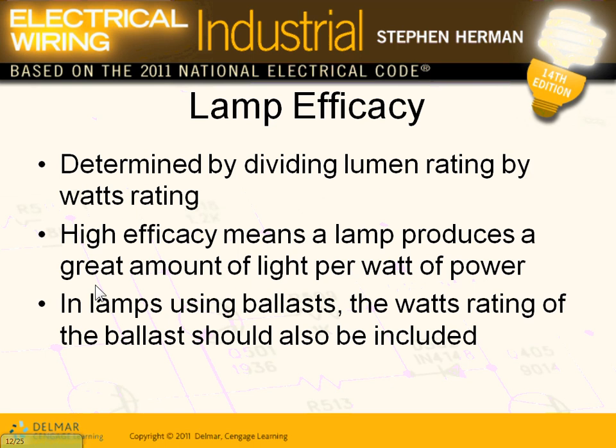Lamp efficacy is a big deal right now because we're becoming environmentally friendly. Efficacy is defined as the lumen per watt — the amount of light per watt. The more lumen per watt I can produce, the better the fixture. It's exactly similar to miles per gallon. The more lumens per watt, the better the fixture I can use.